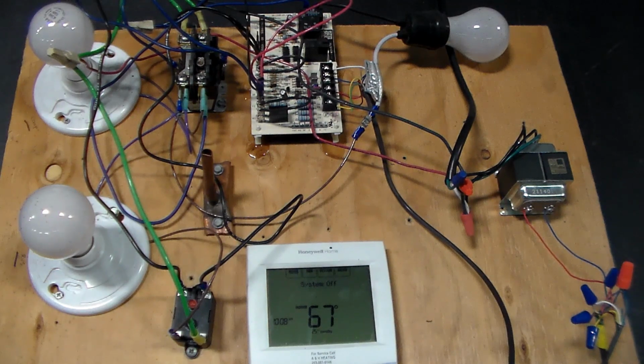Okay, so the Y wire is going to actuate your contactor in either mode, heating or cooling. The O wire is going to actuate your reversing valve, in most cases in the cooling mode. So most units are set up to fail into heat, which means if you call for heat, it's just going to run the contactor, not the reversing valve. And it's going to be automatically in heat mode. When you call for cool, then the thermostat's going to send 24 volts for the contactor and for the reversing valve. And then the board's going to see that. It's going to send power to the contactor and the reversing valve. It's going to reverse the valve into cooling, and you're going to be in cooling mode.